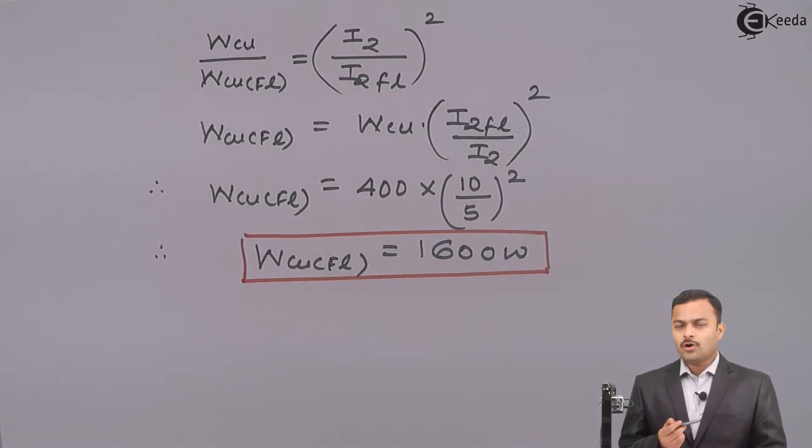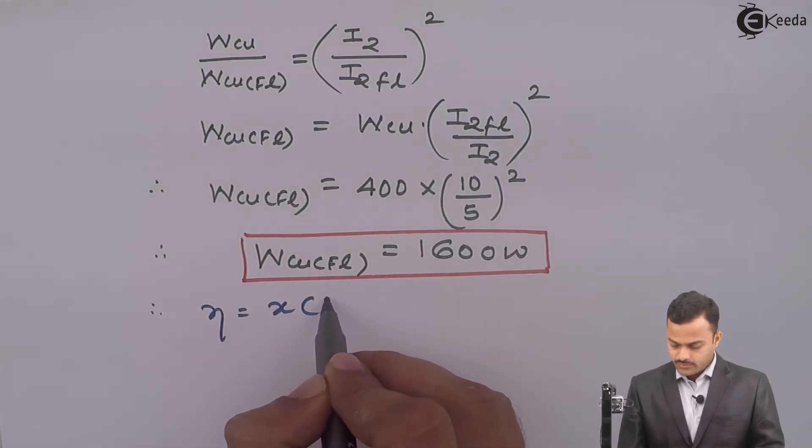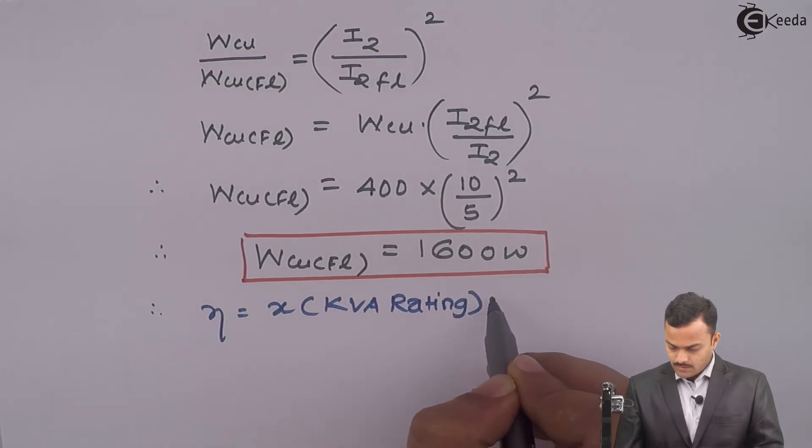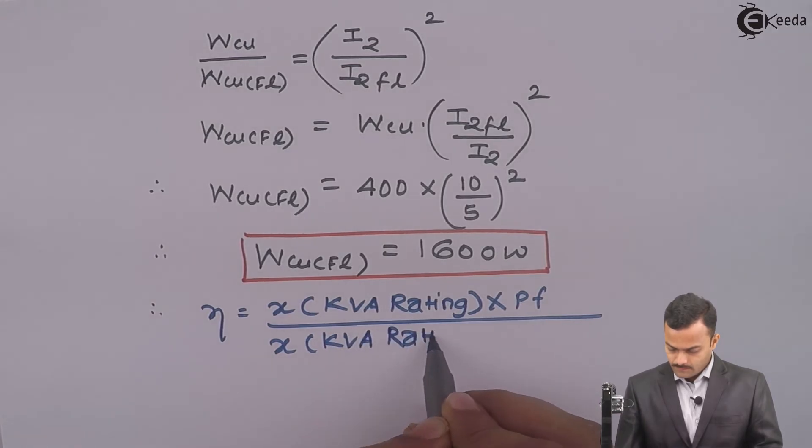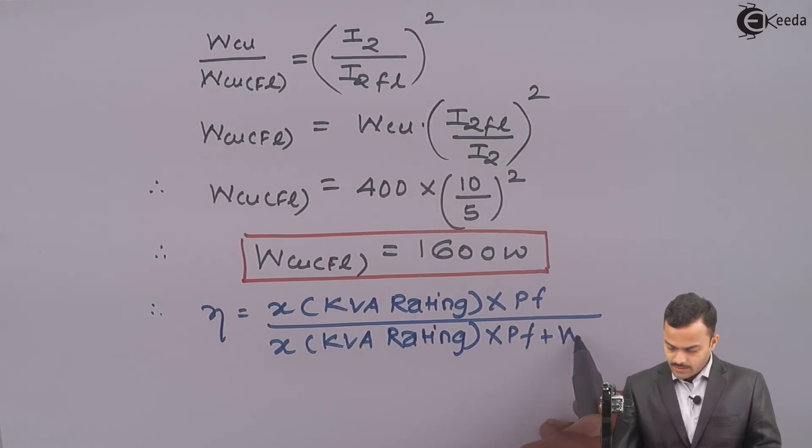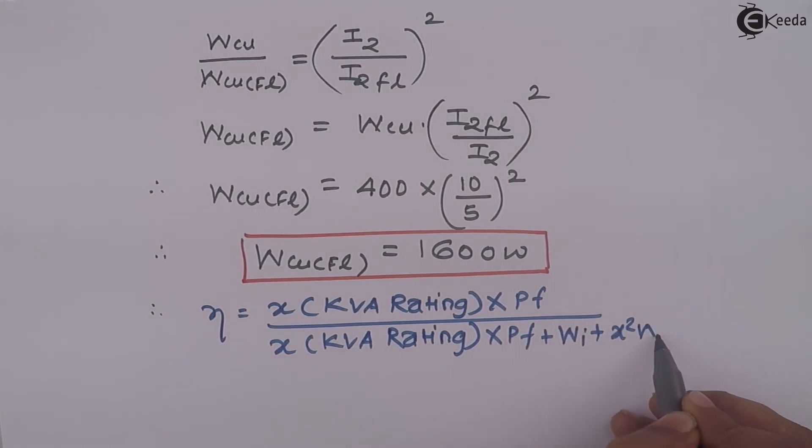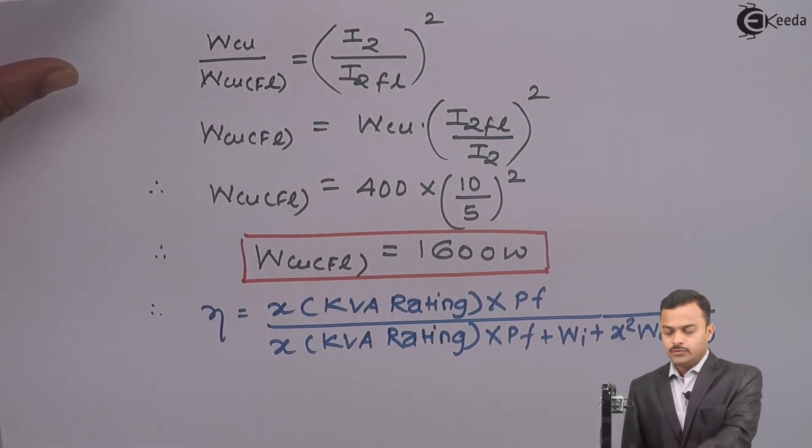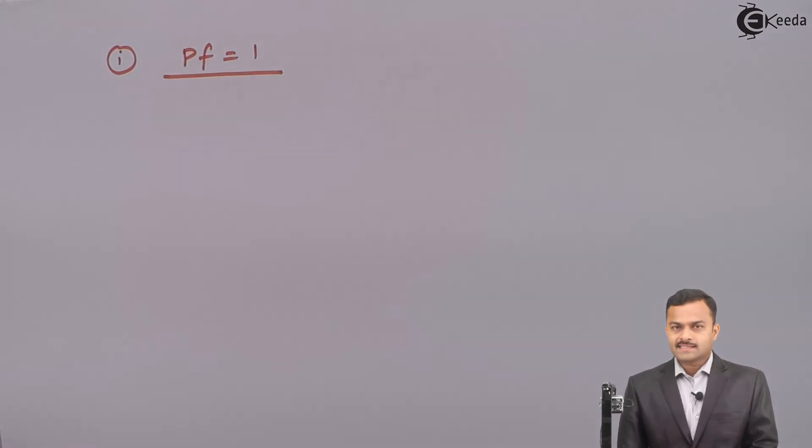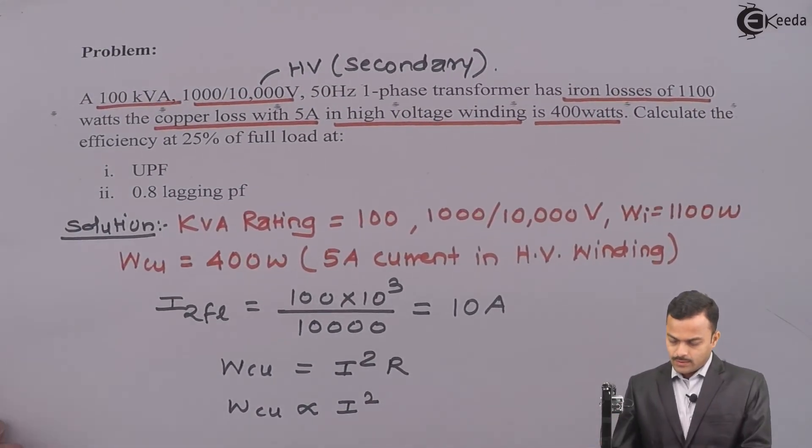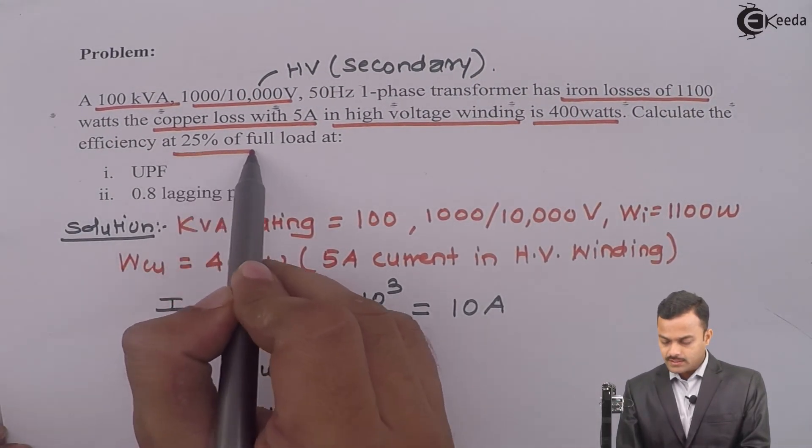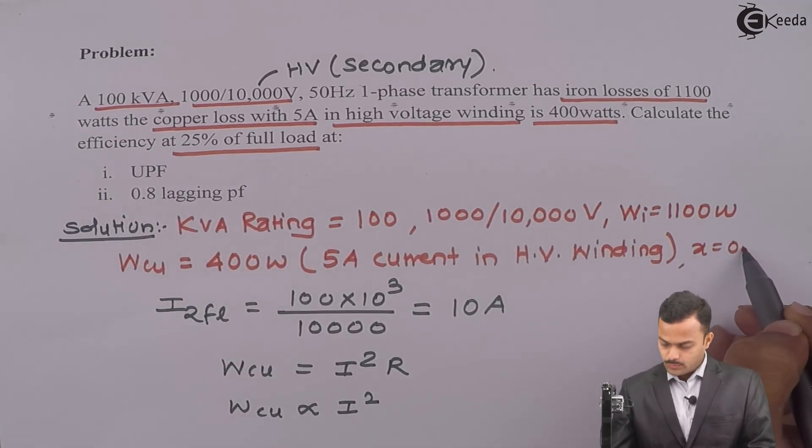Because now only one formula you have to use. And what is that formula? Efficiency is X into KVA rating multiplied by power factor divided by X into KVA rating multiplied by power factor plus iron loss plus X² into WCUFL. So in first case, power factor is 1 and X they have already given. What is the value of X they have given? They said calculate the efficiency at 25% full load. So X is 0.25.